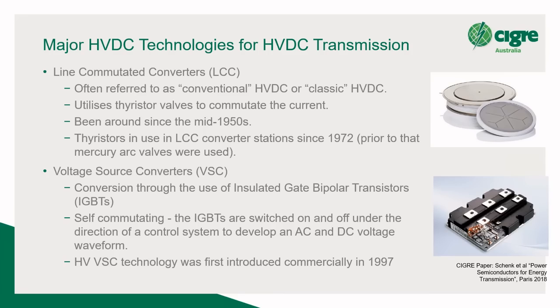From an Australian perspective, if you think about the HVDC links that we have here in Australia, we have two, Direct Link and Murray Link, both VSC converters, whereas Basslink is an LCC converter. And across the ditch into New Zealand, the New Zealand HVDC link is an LCC converter. So VSC, it uses IGBTs, it's self-commutating. So the thyristors and the LCC use the AC voltage to turn on and turn off. And that can lead to some issues, which we'll mention a little bit later. But a VSC is self-commutating. The IGBTs are switched on and off under the direction of a control system.